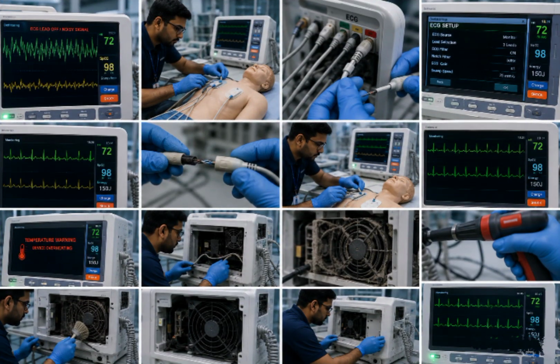The next problem which we might face, as you might have guessed from the image itself, is an ECG signal noise problem. The ECG waveform appears unstable and noisy. You can see in that first image it's very unstable and noisy. So for that you have to check all the ECG lead connections properly. Inspect the cables for any cuts or internal wire damage. Reconnect the leads properly. Adjust the monitor gain and ECG settings. Replace the ECG cables if damaged. Now the ECG waveform becomes stable and clear.